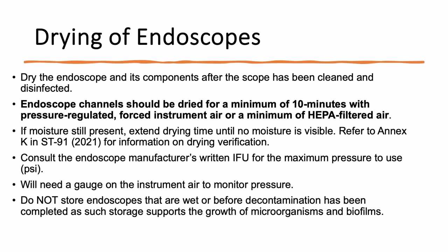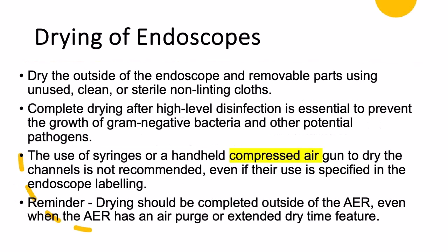You should consult the endoscope manufacturer's instructions for the maximum pressure so you don't damage the scope. You'll need a gauge on the instrument air to monitor the pressure. And never store endoscopes that are wet or before decontamination has been completed. Such storage will support the growth of microorganisms and biofilms. Dry the outside of the endoscope and removable parts, and yet again, you're going to use unused, clean, or sterile non-linting cloths. You complete the drying after high-level disinfection to prevent the growth of gram-negative bacteria and other potential pathogens.